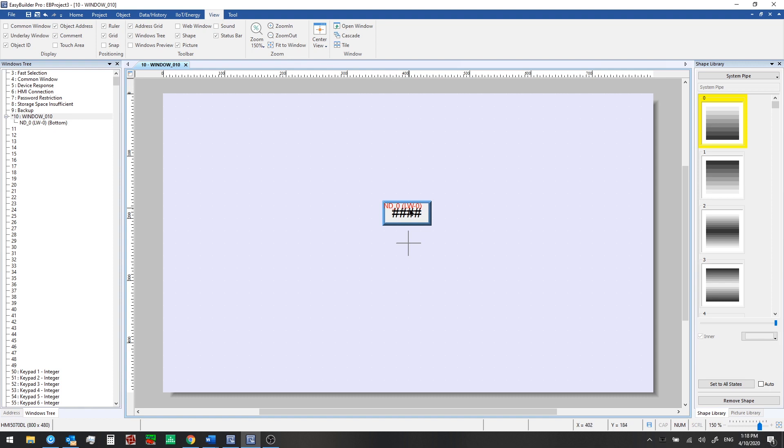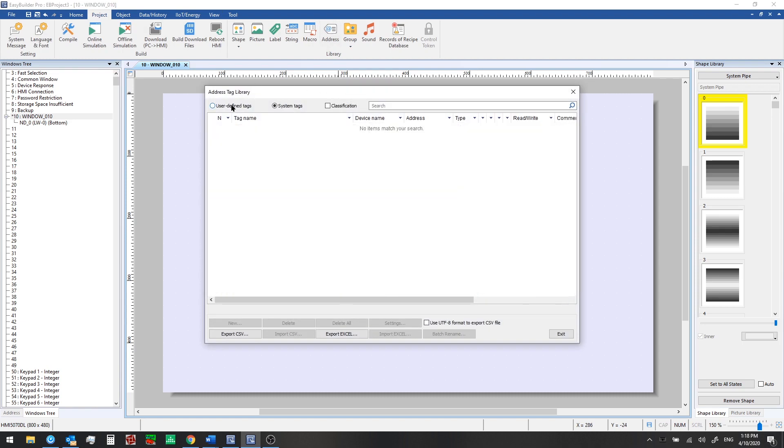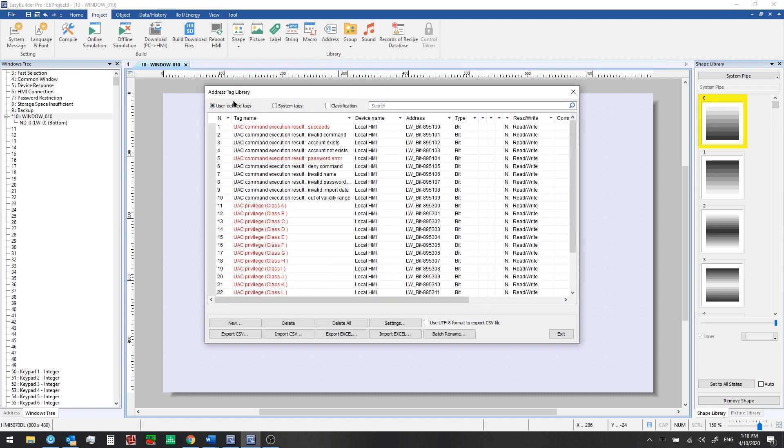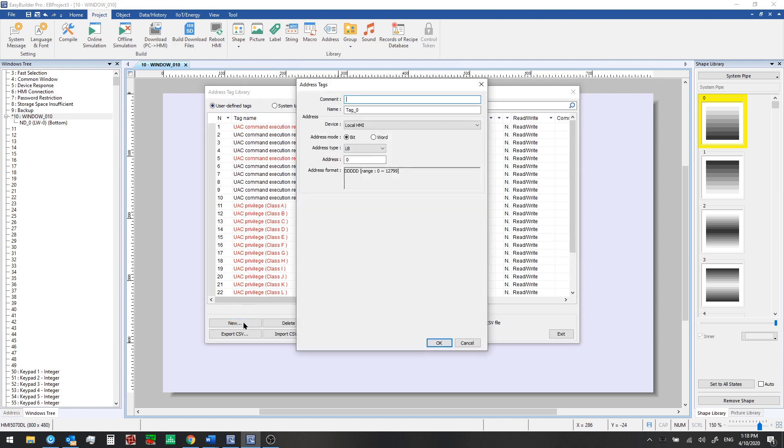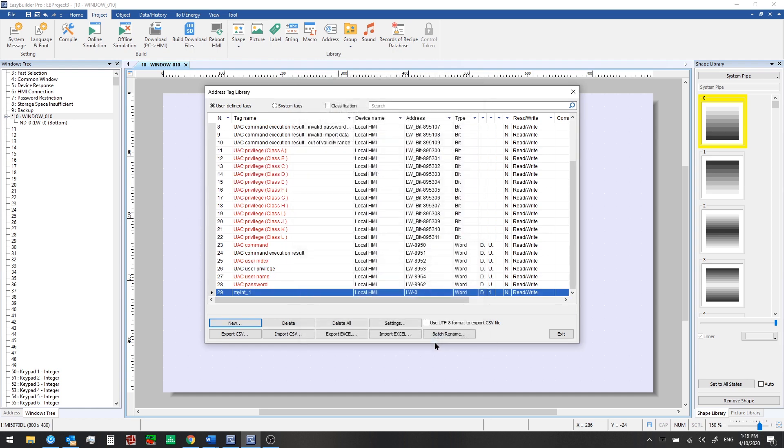But what if we don't want to use this default name, local word? That's not very memorable. So let's go to the project tab and we can just set up a quick user defined tag here. So click on address and then user defined tags. Click new. And here we'll select word for address mode. And we already have local word zero set there. Let's go ahead and name this. It's an integer, so we'll go ahead and call it my int one. And you can select the data format that you would expect it to be here. So 16 bit unsigned is what we'll pick. And go ahead and click OK. Now we see this in our list of user defined tags. So you can use these if you'd like. Click exit.